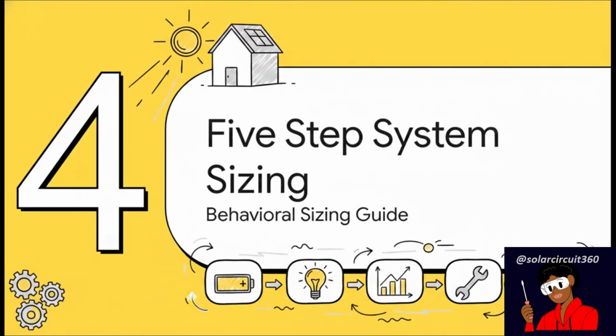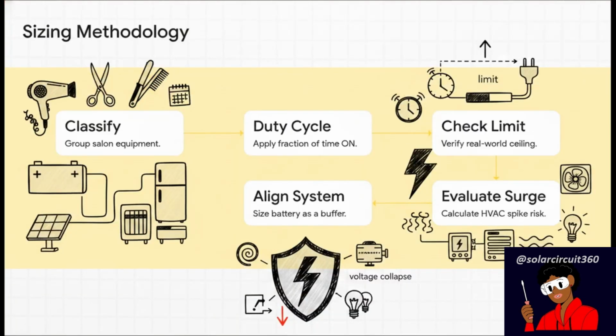Which perfectly sets up Section 4, the 5-step system sizing. This is our behavioral sizing playbook. Okay, here is the pragmatic, step-by-step playbook for actually engineering a safe, reliable system. Step 1, classify your load groups. Step 2, apply the duty cycle reality, meaning account for the actual fraction of time a device is physically switched on. Step 3, check that inverter ceiling, keeping that real-world 6.4 kilowatt limit in mind. Step 4, evaluate your surge stacking risk by calculating the probability of that massive HVAC spike overlapping with your heavy resistive loads. And Step 5, align your battery and solar.